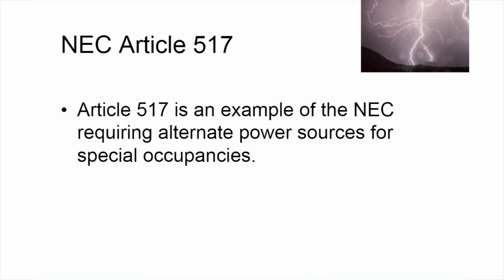Now they start introducing the term essential electrical systems. Essential electrical systems for hospitals are comprised of 3 separate branches supplying a limited amount of lighting and power, and they're considered essential for life safety and effective hospital operation during the time of normal electrical service interruption. The 3 branches are life safety, critical, and equipment. So the life safety falls into one classification with NFPA 110, while the others fall into another. And so it's very important that you understand what types of equipment will be provided by each of these branches and how you interconnect those from a NFPA 110 standpoint and also an Article 700 and 701 standpoint.